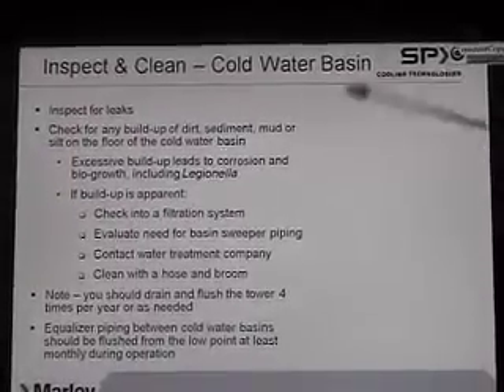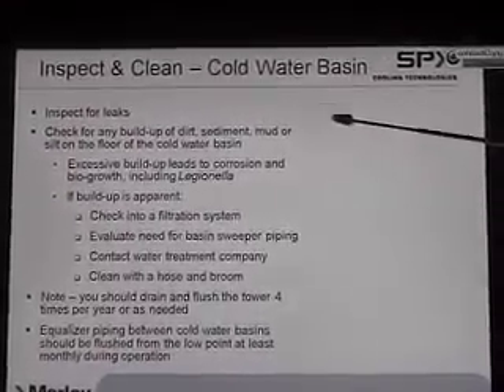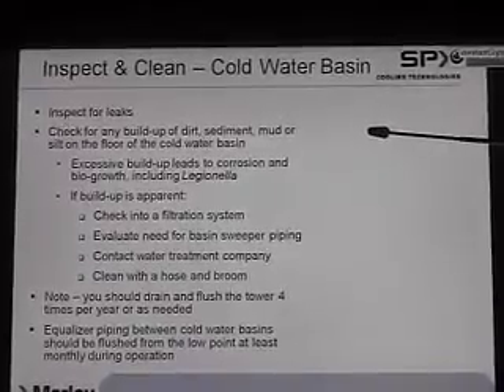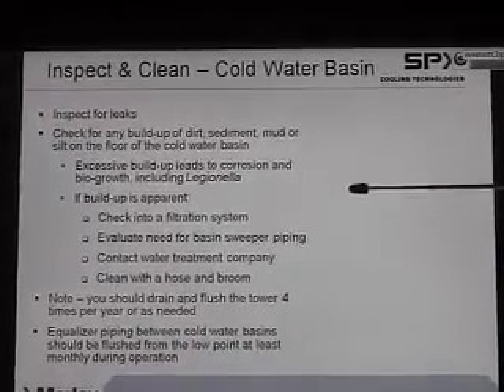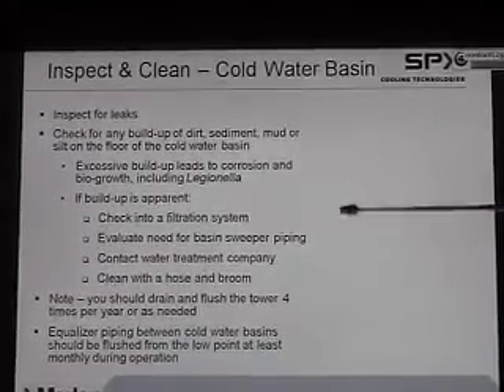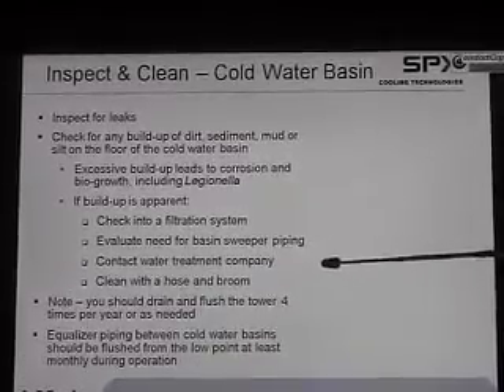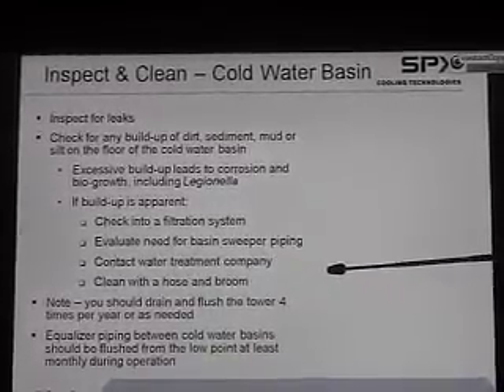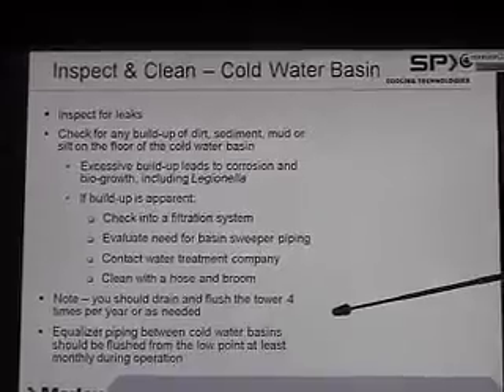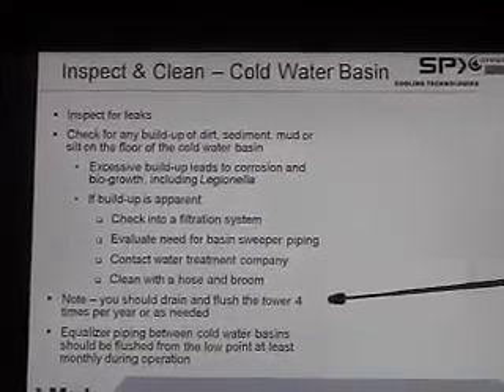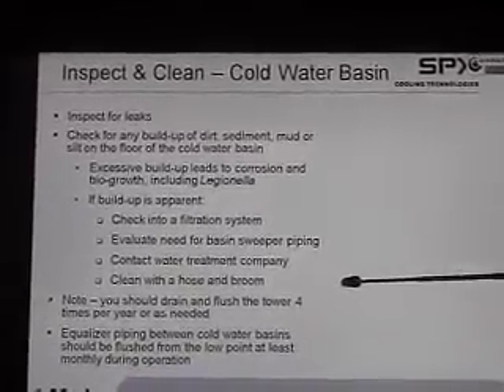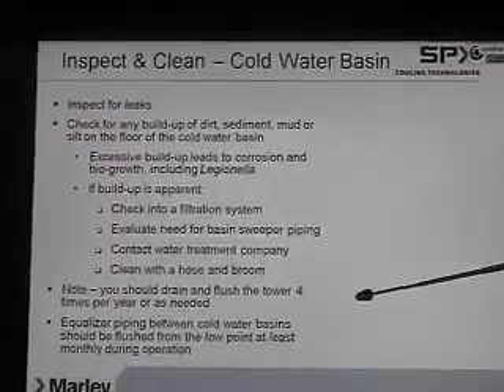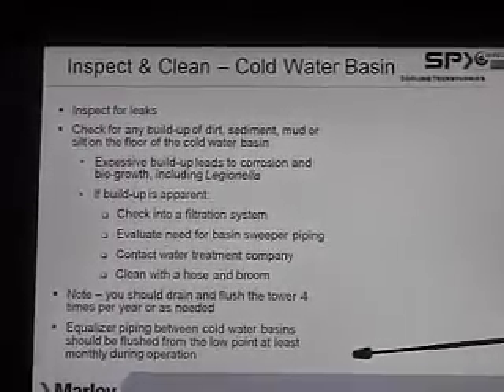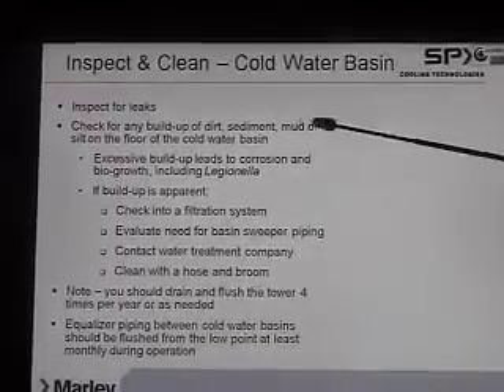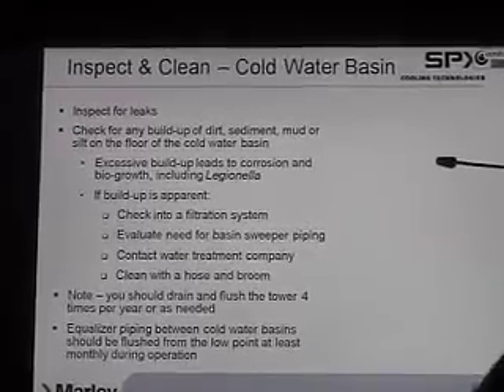Say you want to inspect your cold water basin for leaks. Again, a water filtration system, basin cleaning, sweeping system would be excellent. Clean with a hose and a broom. You'd have to drain and flush the tower and do all the chemicals again. And don't forget your equalizing piping between the cells.